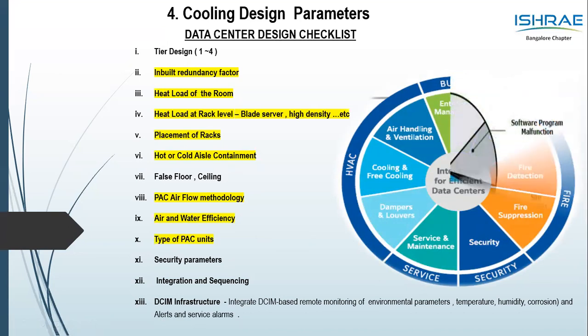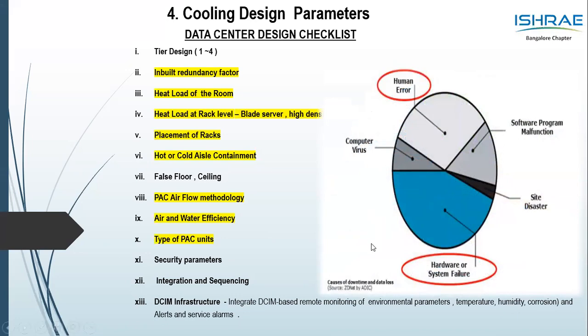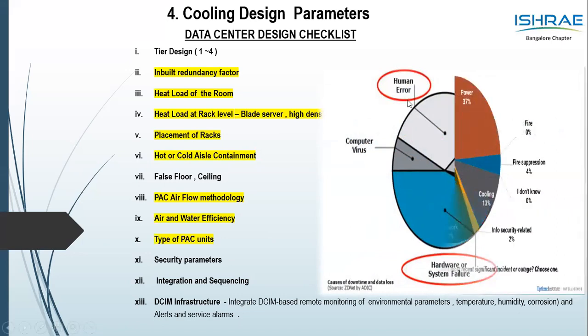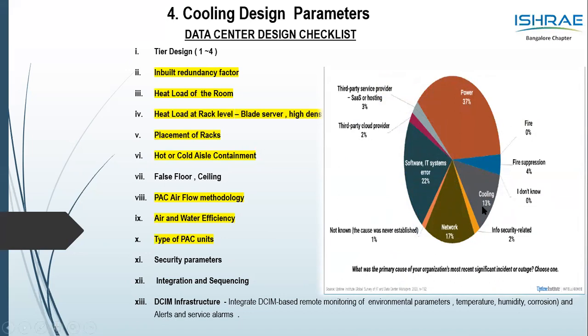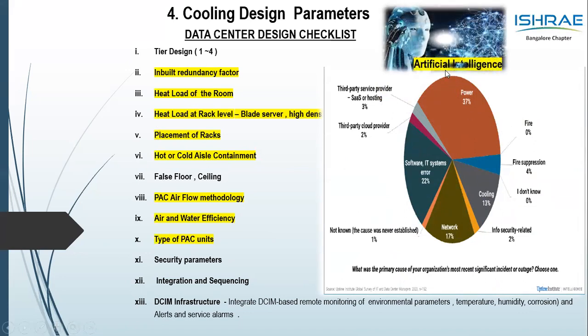Why I say that is that the report says the cause of downtime in a data center is, unfortunately, apart from hardware and system failure, also due to human failure. And human failure, again, the next report says that for the cooling unit and power, of course, power is 37%, but a wrong cooling unit accounts for 13%, which is again a worrying factor. I have a slide on every one of these highlighted points. Having artificial intelligence to monitor all of these parameters is very important, and also designing the right cooling unit would actually reduce this percentage in the coming years.